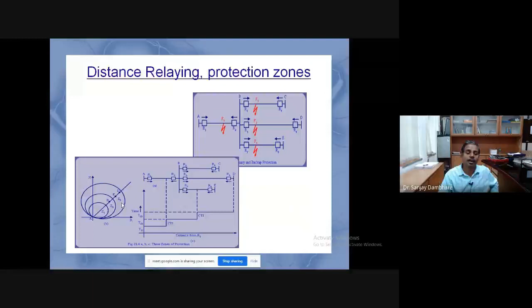These protective relays are very badly affected by what is called load encroachment. So what happens when the load on the system increases? The operating point, which otherwise would have been at this place in this particular region, goes traveling into this particular part. And if this operating point, because of the increase in load, goes and stays for sufficient time in any of the zones, then that zone may trip, because the relay has some setting. If the operating point stays here for more time, it may trip zone 3 or zone 2, and this particular problem is called load encroachment.